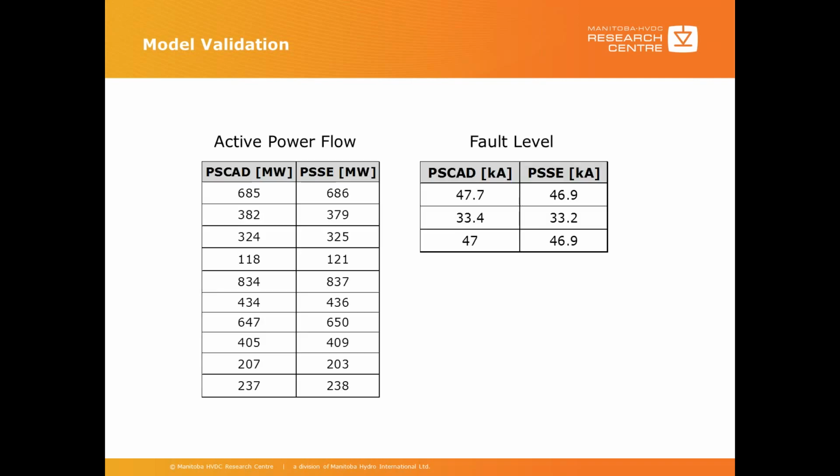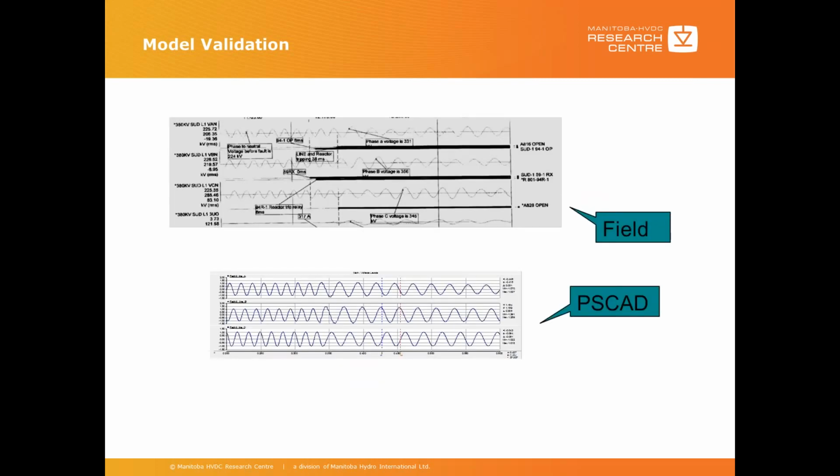In this example, the load flow and fault level compared with other load flow programs such as PSSE. As we can see in the tables for the power flow and fault level, they're pretty close. And they are within the acceptable range. Here in this example, we are comparing the PSCAD results with the field measurements. And we'll see they're in a good standing.